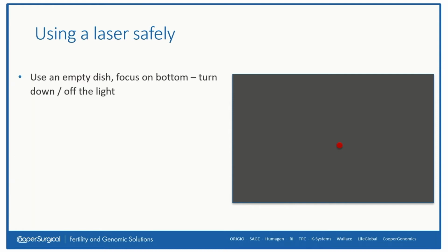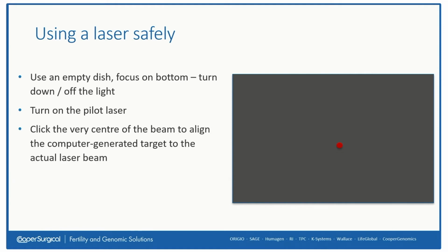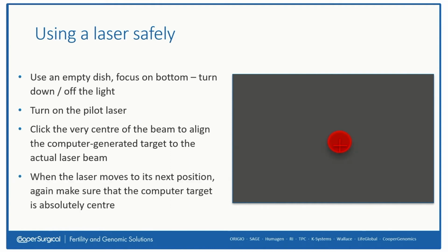So as a manufacturer then, we would recommend these steps. First, get an empty dish and focus on a scratch or something on the bottom inside surface. You may want to turn off or turn down the light to better see the laser guide or the pilot laser. So follow your manufacturer's guidelines. In the case of the Saturn laser, you need to click the center of the red pilot beam. And when it moves through to the next 6 positions, in the case of an active laser, you click exactly in the center. In this way, we teach the computer how to move the laser to get to the particular part of the screen we want it to fire at.